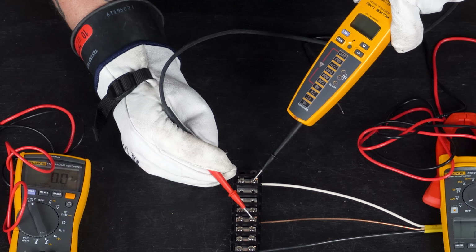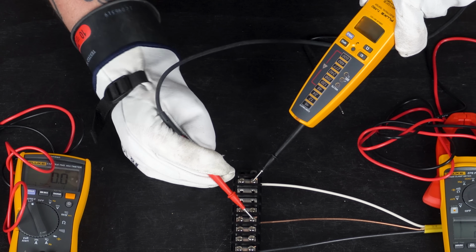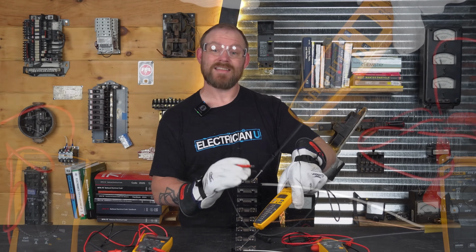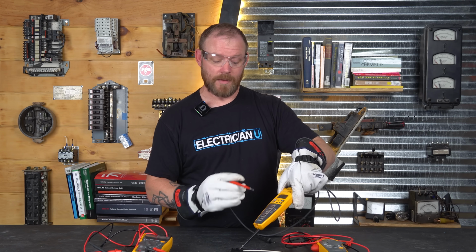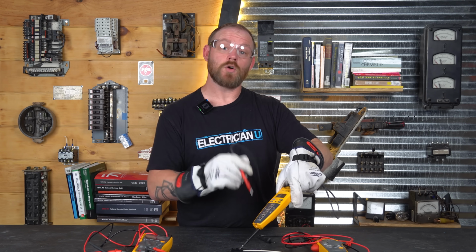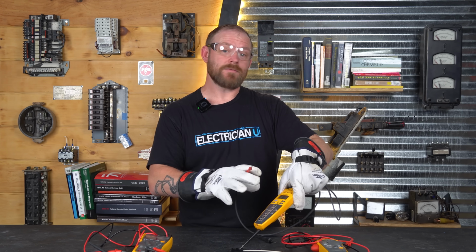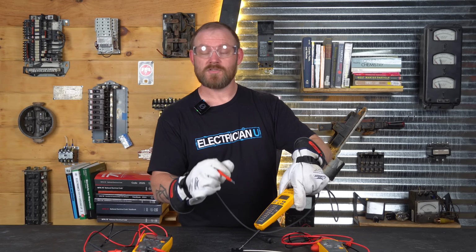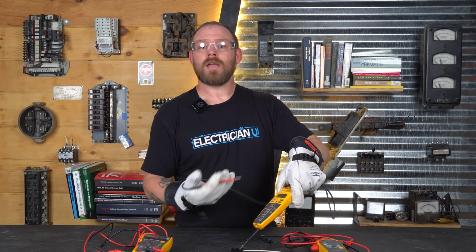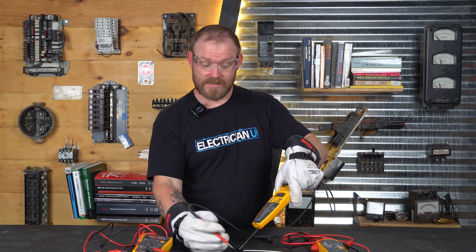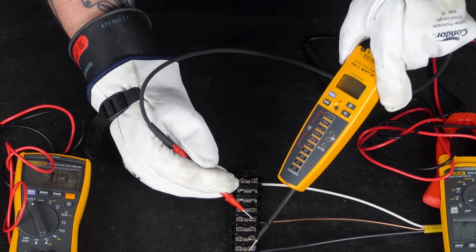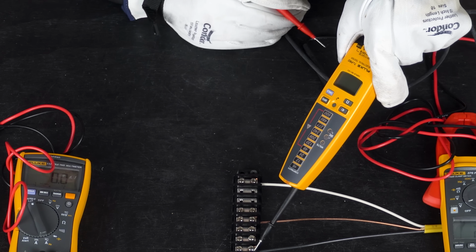But if I have a ghost voltage, it doesn't light up. The screen's trying to illuminate, because there's certain voltage thresholds that it needs to get to be able to illuminate. But this specifically has a low Z mode as it is. So it already has a low enough impedance that it kind of drains off any current in a ghost voltage situation, where it's just going to eat that ghost voltage up. And it's going to tell you, okay, yeah, what you have here is a ghost voltage. You don't have an actual real voltage.